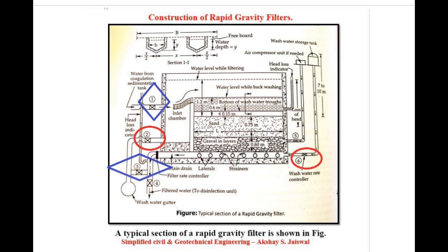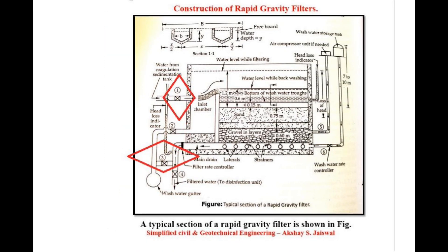After the washing of the filter has been completed, valve 2 and 6 will be closed and valve number 1 and 3 are opened. This restores the inlet supplies through valve 1, but the filtered water in the beginning is not collected and is washed for a few minutes through valve number 3 to the gutter. This is necessary because the remains of wash water must be removed from voids of the filter and a surface mat must be allowed to be formed on the sand.